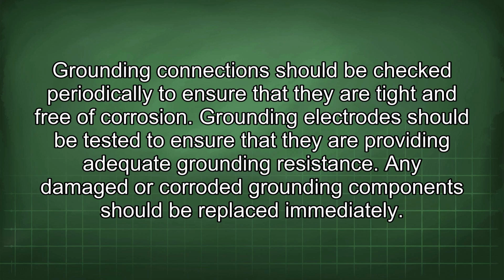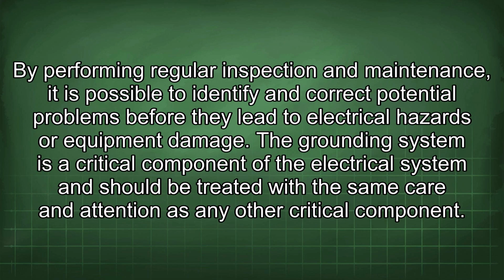Grounding electrodes should be tested to ensure that they are providing adequate grounding resistance. Any damaged or corroded grounding component should be replaced immediately. By performing regular inspection and maintenance, it is possible to identify and correct potential problems before they lead to electrical hazards or equipment damage. The grounding system is a critical component of the electrical system and should be treated with the same care and attention as any other critical component.